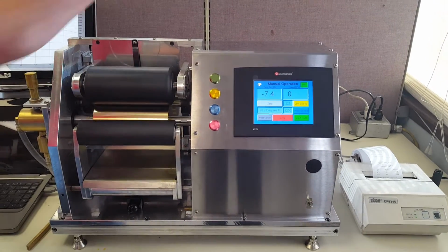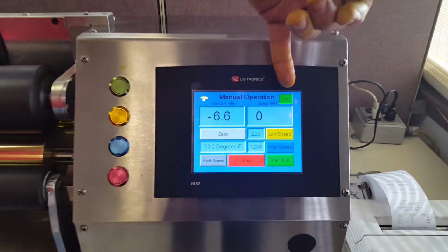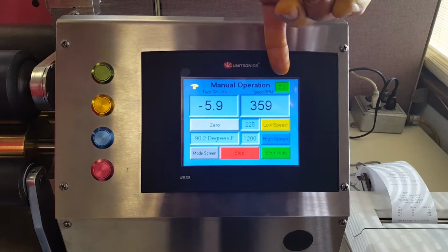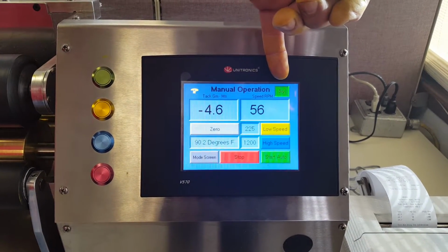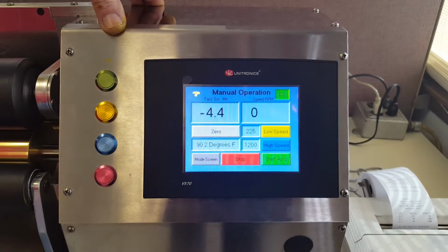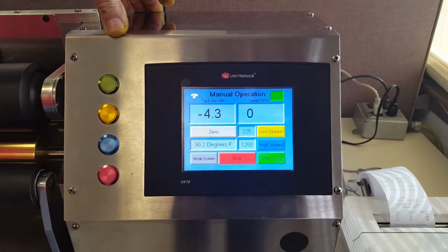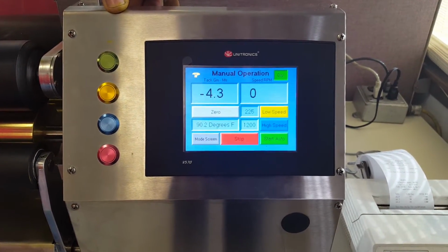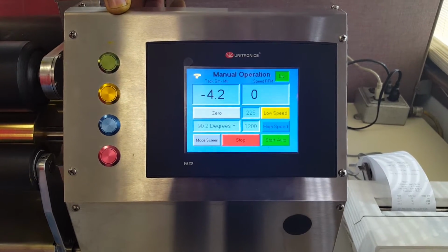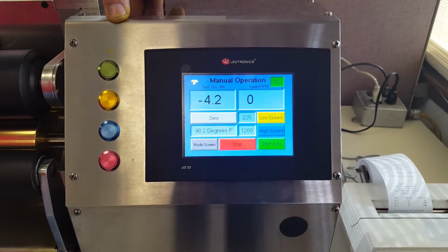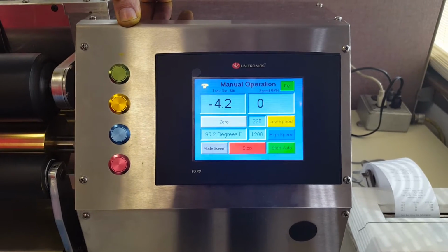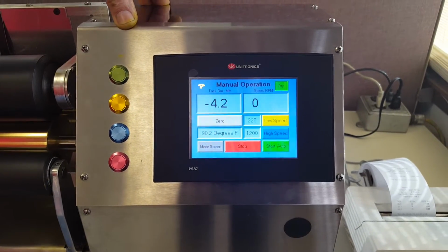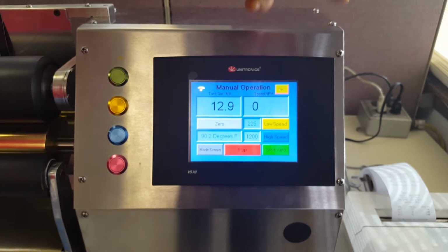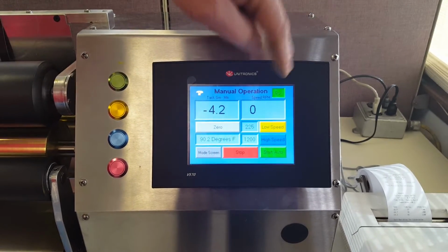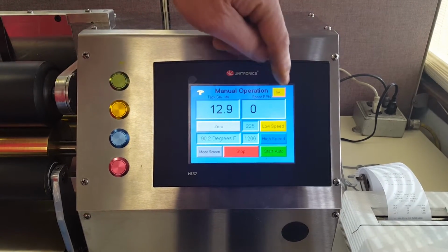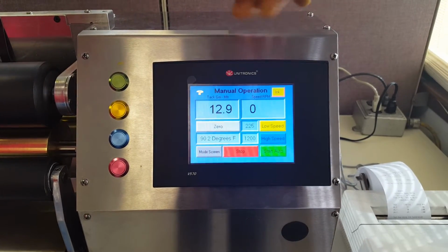Now, one other feature we have: you'll see there's a rectangle labeled dry, colored green at the moment. As you'll find out in the technical discussion, there are actually two methods of calibrating this machine. We can calibrate it with a tack standard ink, which is an ink calibration, or with a calibration bar, which is a dry calibration. I have the ability to select which calibration method I want to use simply by touching this button here—you'll see it says ink, so that would be ink standard.